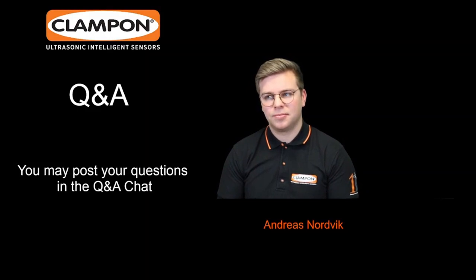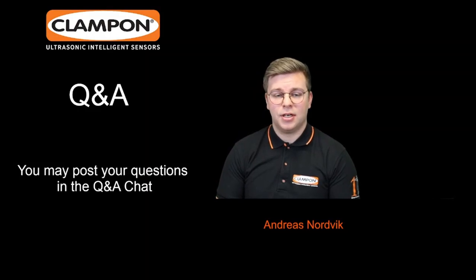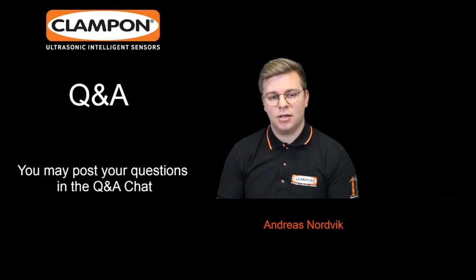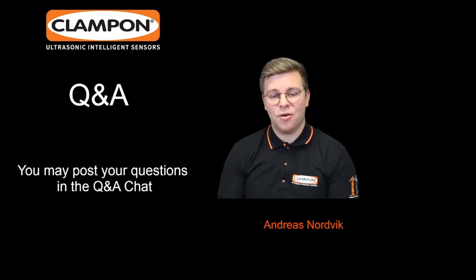Thank you. Moving on, Jack has a question. Any limitation on the umbilical length? That depends on the protocol you're running on. If you have CANopen, I think it's around 40 meters. We recommend not to go above.